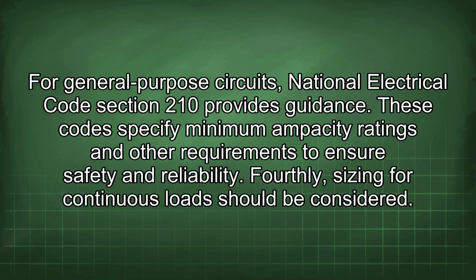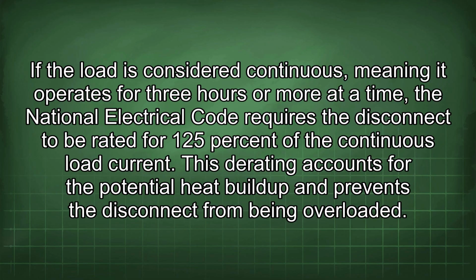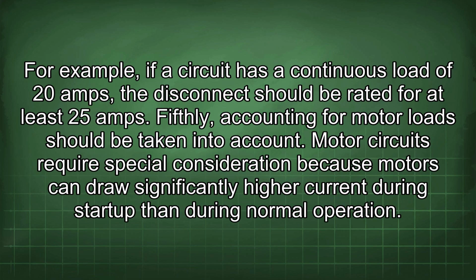Fourthly, sizing for continuous loads should be considered. If the load is considered continuous, meaning it operates for 3 hours or more at a time, the National Electrical Code requires the disconnect to be rated for 125% of the continuous load current. This derating accounts for the potential heat buildup and prevents the disconnect from being overloaded. For example, if a circuit has a continuous load of 20 amps, the disconnect should be rated for at least 25 amps. Fifthly, accounting for motor load should be taken into account.